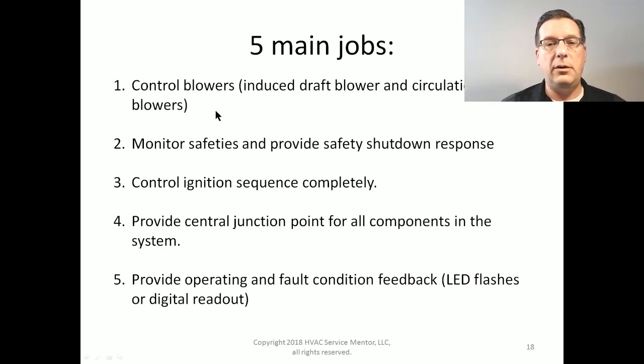So check this out. The blowers, those are outputs, right? Igniter, that's an output. Gas valve, that's an output. So for all those outputs, there has to be a voltage supply, right? So if it's a 120 volt blower, there has to be 120 volts coming in. Is it there? Ignition sequence, igniter, there's got to be 120 volts coming in. Is it there? Junction point, pretty obvious. Gas valve, that's 24 volts. There's got to be 24 volts coming in. Monitor safeties and provide safety shutdown response. Those are going to be our voltage send and voltage return, digital binary inputs. There may also be, in the case of a modulating furnace, a draft pressure transmitter that is sending a value. And then that value is going to be used to control the speed of the draft inducer.